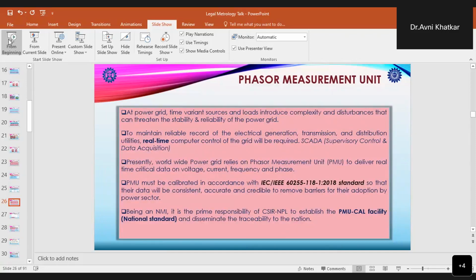And at the power grid, the time variant sources and loads introduce complexity and disturbances which can threaten the stability and reliability of the power grid. And in order to maintain the reliability of electrical generation, transmission and distribution, real time computer control of the grid is required. Initially SCADA was used. Now worldwide, the power grid is moving towards the concept of phasor measurement units in order to deliver real-time critical data on voltage, current, frequency, and phase. And these PMUs are so important because they are providing all the information of the grid.